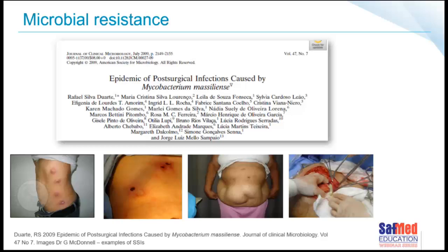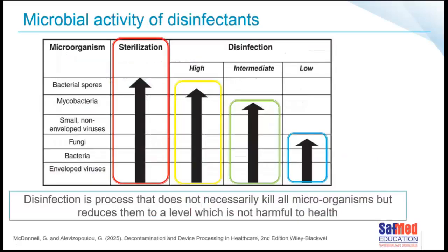And the outbreak was, in fact, linked to the use of a 2% glutaraldehyde at the time, that was used to disinfect the laparoscopic instruments. You can see on the images over here where sepsis formed, where these abscesses formed, and long after the original case, up to 6 months later, in fact, and they then realized that this particular microorganism had become resistant to this 2% glutaraldehyde. A huge outbreak back in the day when we were still soaking a lot of our ports and our laparoscopic instruments. Hopefully we've moved on and those instruments are now these days being sterilized.